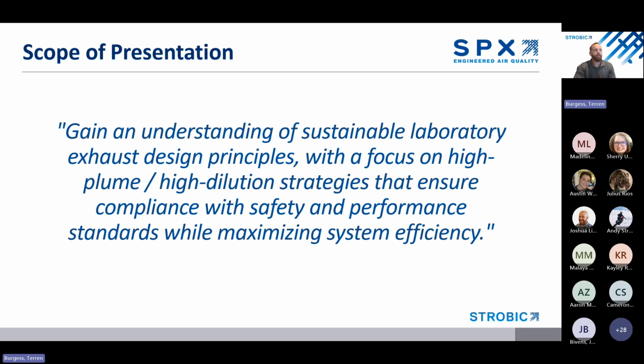that ensure compliance with safety and performance standards are being met while maximizing the efficiency of the system. So when we think about labs, right, labs often have high volumetric flow rates for safety, which means huge volumes of conditioned air being exhausted outdoors. So exhaust fans typically could run 24/7 in many facilities, which is going to create a very energy intensive environment. So sustainable design aims to reduce fan energy, heating and cooling load, and overall carbon footprint, all while maintaining safety and compliance that's going to be required in these critical environments.